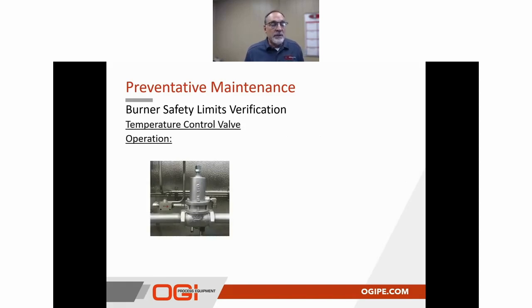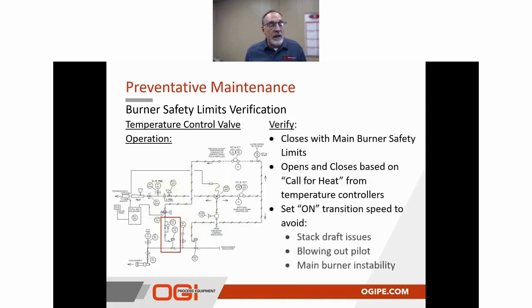We also want to make sure about the functionality of the temperature control valve. In this case, we want to verify that the control valve will close when the main burner safety limits aren't satisfied. So when there's a burner-specific or a general safety shutdown, that valve is also closing. We also want to make sure that valve opens and closes when there's a call for heat from a temperature controller, and that the on-transition speed avoids any potential stack draft issues, any potential problems with blowing the pilot out, or that the transition isn't too quick that it actually causes main burner instability.